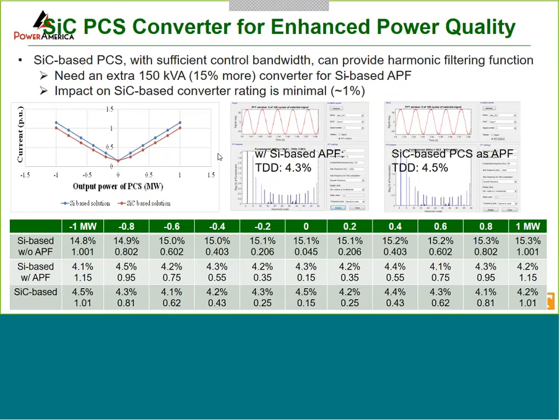So we compared the silicon-based approach with the silicon carbide-based approach. With the silicon-based approach, because of its limited bandwidth, if you have some harmonic load, you would have to add an additional filter, either a passive filter or an active filter with higher control bandwidth than what a medium voltage silicon IGBT can provide. The difference because of that is about 15% more converter rating if you use a silicon-based approach. With silicon carbide, that can be inherently provided with very little impact on the rating, just about 1%. And in both cases, we can achieve similar THD or TDD.